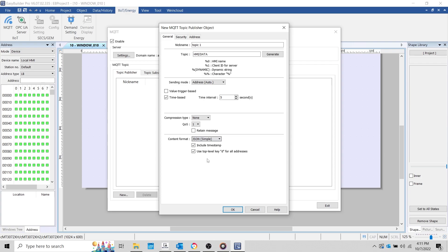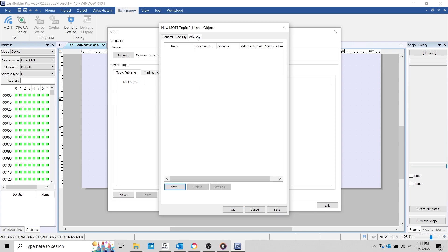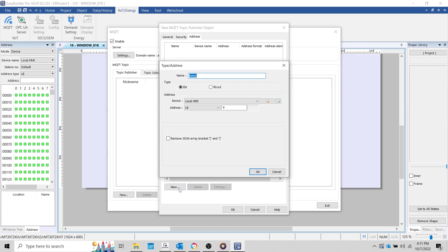The options below JSON Simple will allow you to add a timestamp to the message, or make each address a property of an address titled D. This feature was created to prevent the timestamp from appearing as an address name. I'll leave both options selected, and we'll add an address to monitor within the Address tab. To do this, I'll select New, and we'll monitor one of the HMI's internal bits, LB0. We can call this value Data. With that finished, I'll click OK, and we'll define a new message to publish.